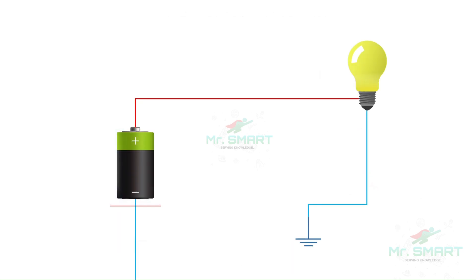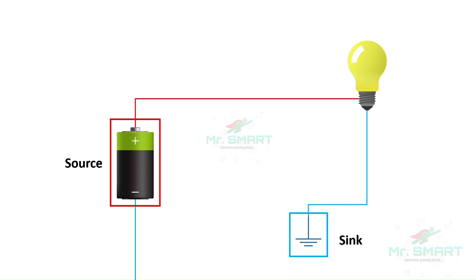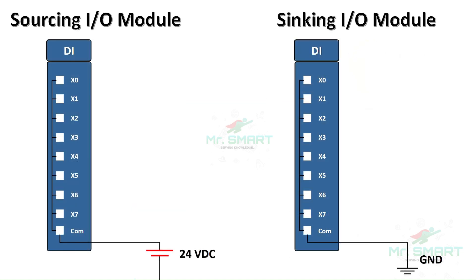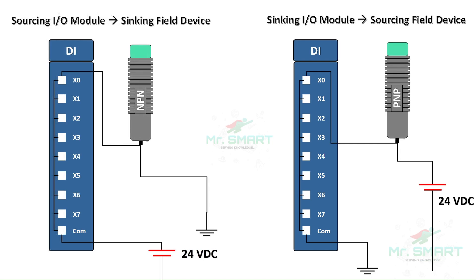So it's crucial to make sure the sourcing and sinking configurations are correct. Let's quickly summarize the key points: Source provides current; sink provides the ground path for current to flow. In a sinking I/O module, the module provides the ground. In a sourcing I/O module, the module provides the current. A sourcing field device must connect to a sinking I/O module. A sinking field device must connect to a sourcing I/O module. Mismatching sourcing and sinking devices with I/O modules can cause circuit failures.